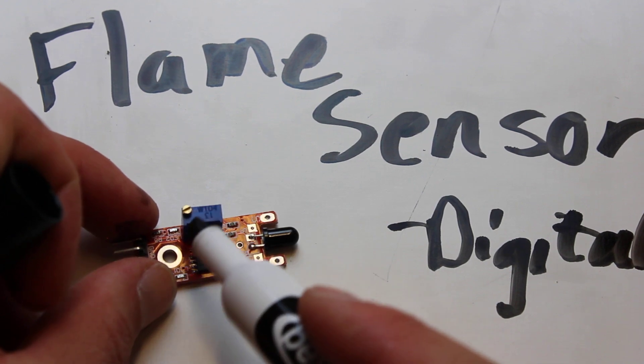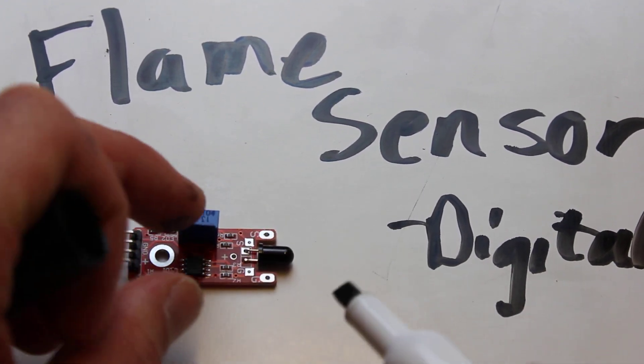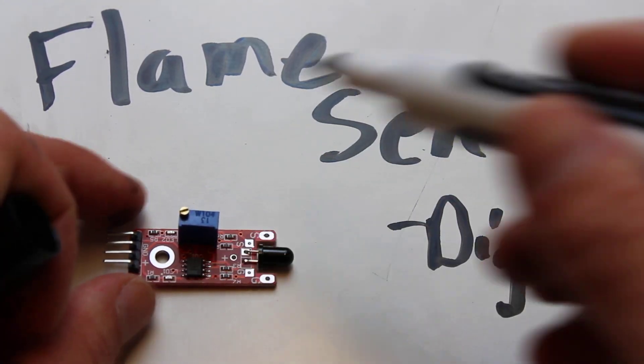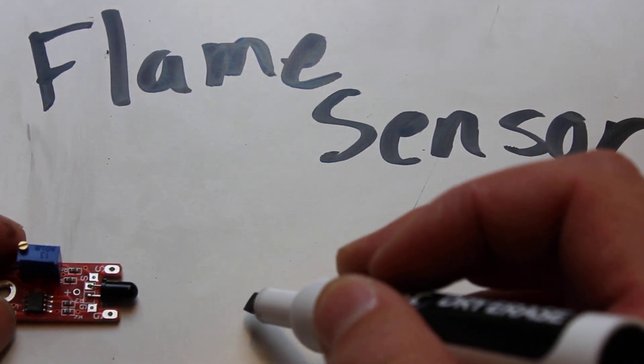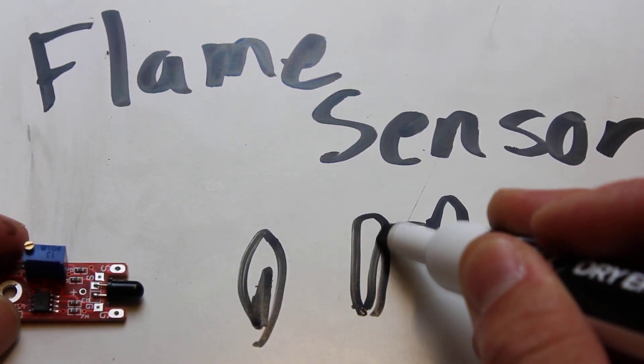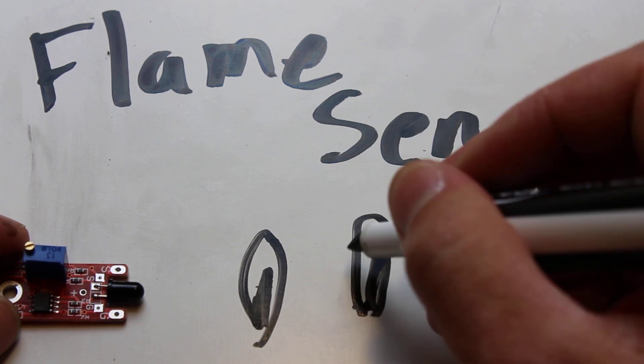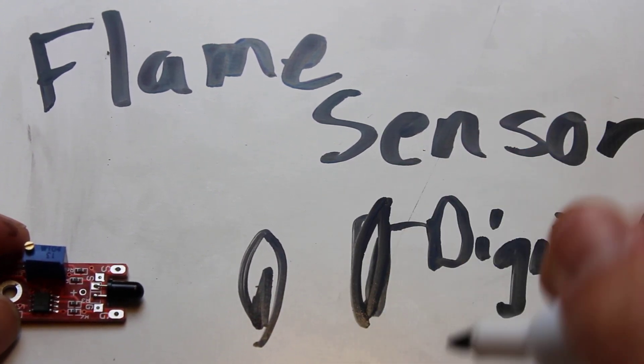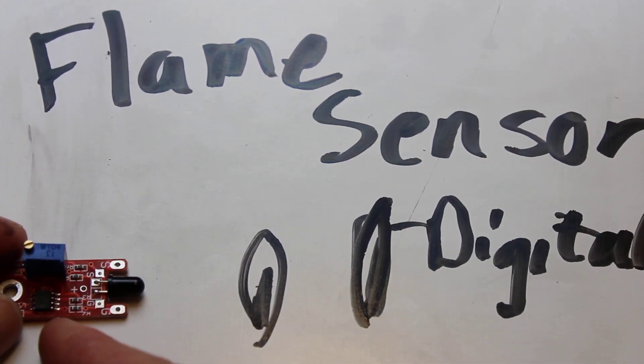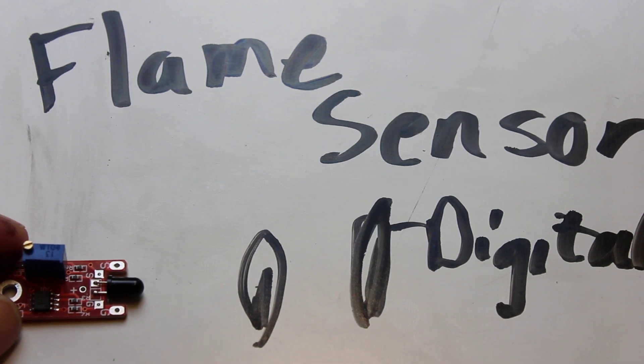That potentiometer - this blue box right here - is for varying the range. Do you detect a flame right here, or can you detect a flame further out by adjusting the potentiometer and changing the distance? That potentiometer changes the range at which you detect flame.